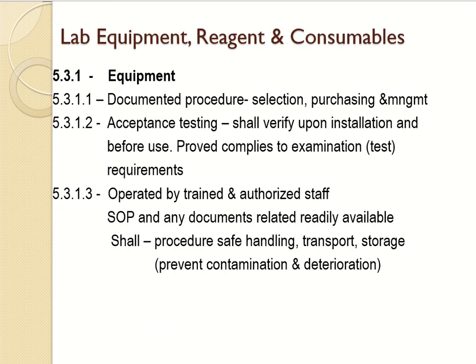Now we go on to the next clause 5.3, lab equipment, reagent, and consumables. Under clause 5.3.1.1, they should have documented procedure for selection and purchasing and management of these items. Acceptance testing shall verify upon installation and before use, proving that it complies to examination requirement, and it should be operated by trained and authorized staff.